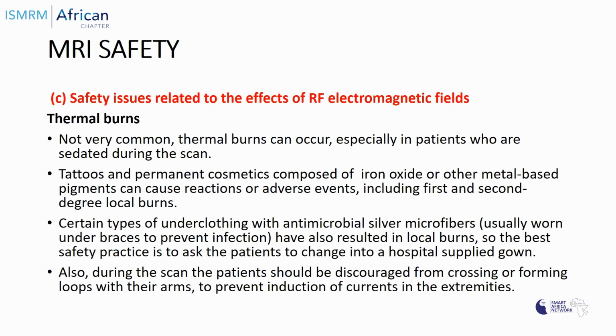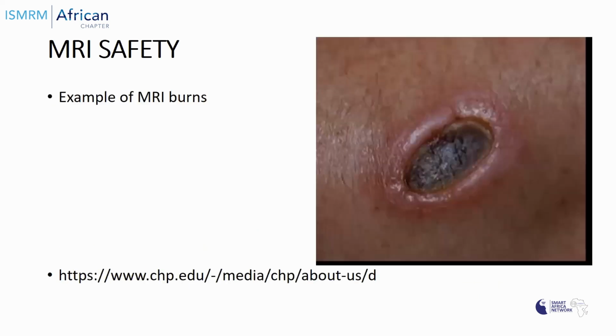Tattoos and permanent cosmetics composed of iron oxide or other metal-based pigments can cause reactions or adverse events, including first and second degree local burns. And also certain types of underclothing with antimicrobial silver microfibers have resulted in local burns. So the best safety practice is to ask the patients to change into a hospital supplied gown. Also during the scan, the patient should be discouraged from crossing or forming loops with their arms to prevent the induction of current in the extremities.